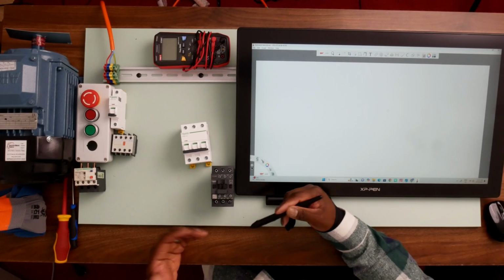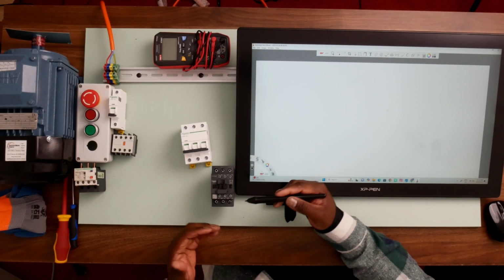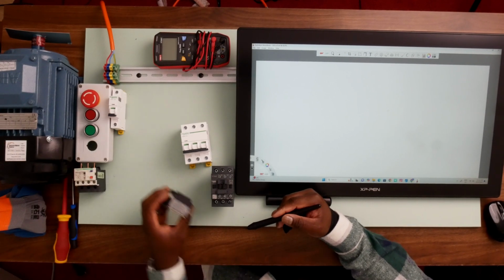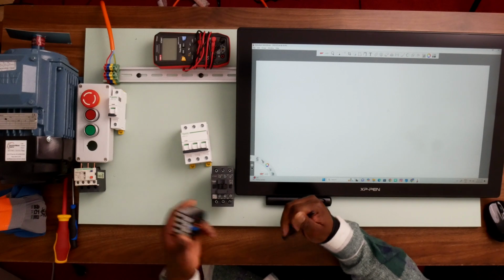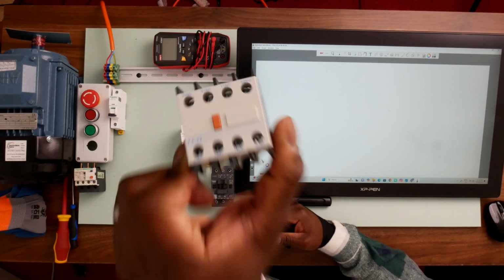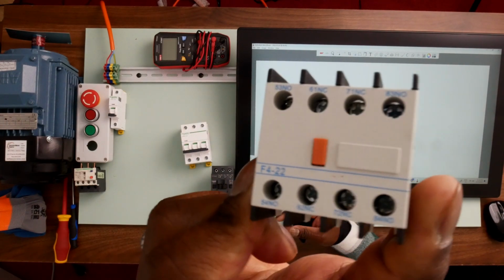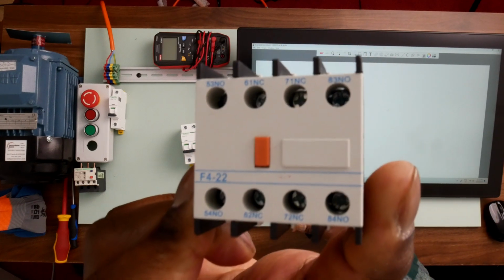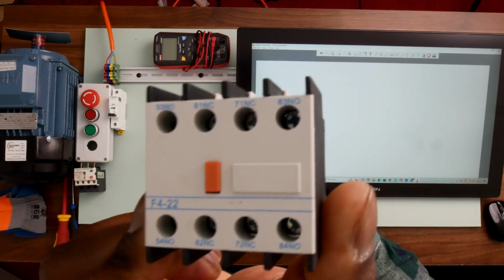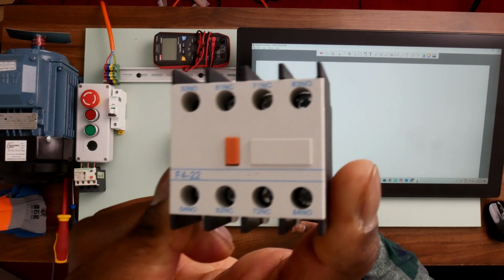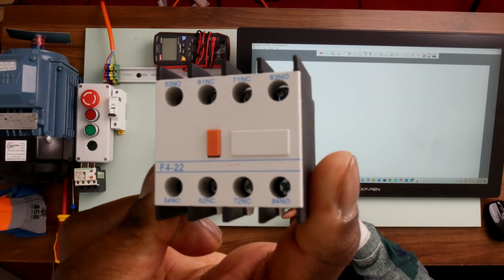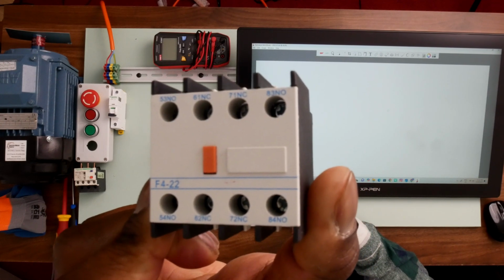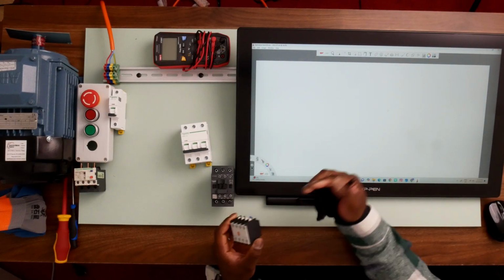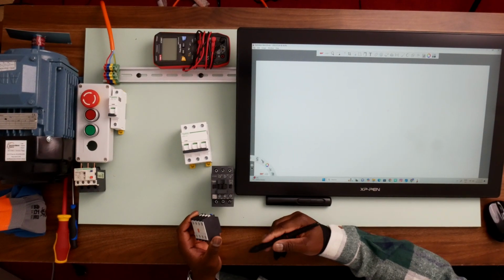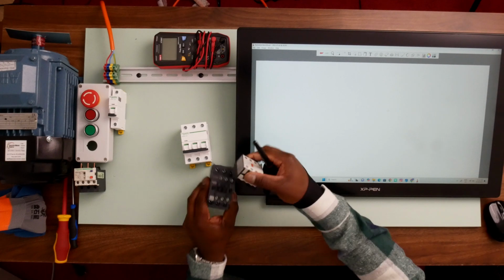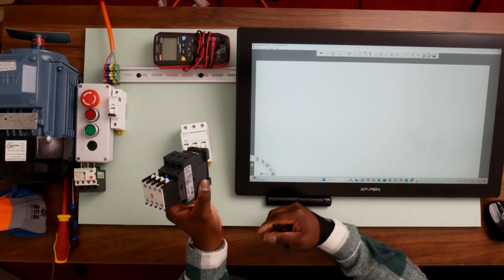But if this contactor didn't come with auxiliary contacts built onto it, or we needed additional normally closed or normally open contacts for interlocking with other equipment, we could use external or clip-on auxiliary contacts like this one. This one has two sets of normally open contacts, which are on the outside, and two sets of normally closed contacts, which are on the inside. So this is an auxiliary contact block that we can use for other interlocking purposes, and we simply clip it on to the contactor like this.